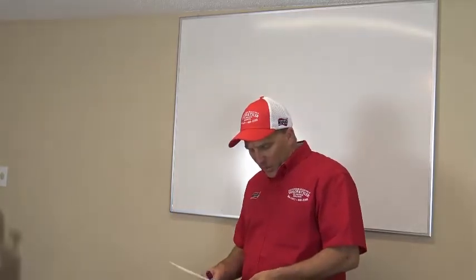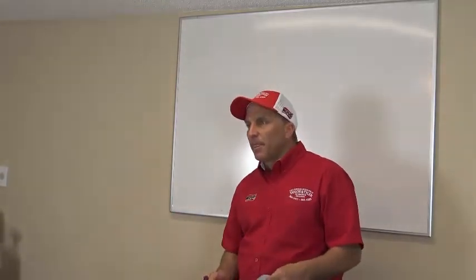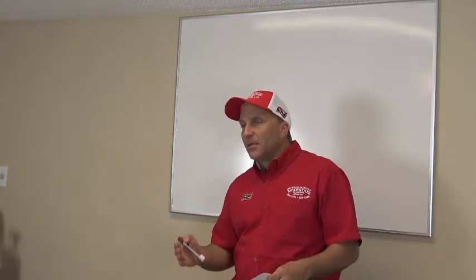Time delay. Is it okay? Is it shorted or there's none? Time delays are a lost art in this business, guys. I never see a time delay on a system. What is a time delay for? Compressor, right? It's basically stopping the compressor from short cycling, okay?